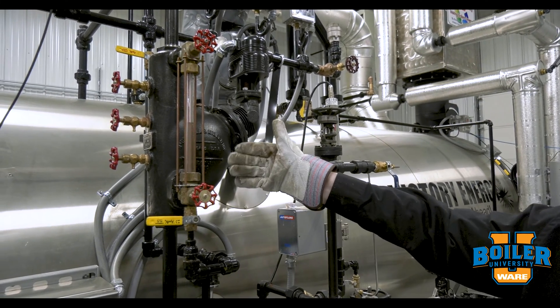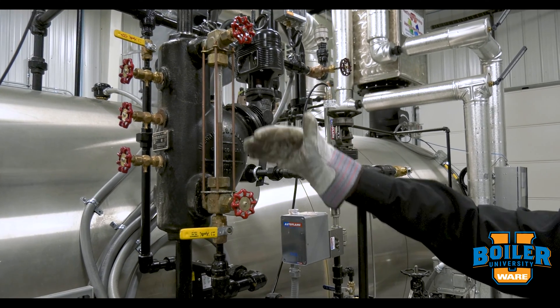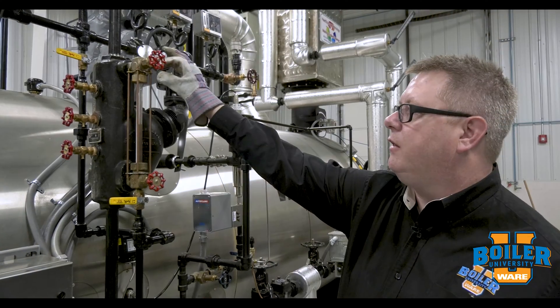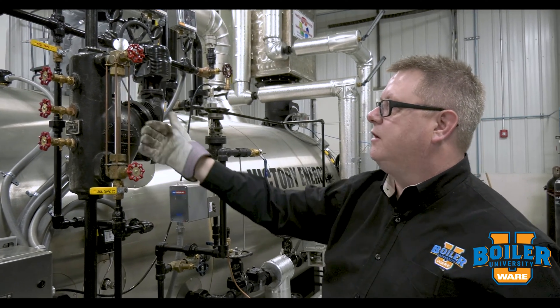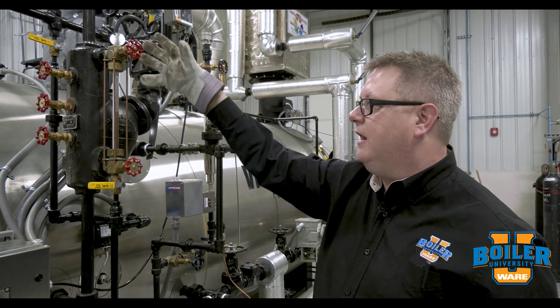Now occasionally when I blow down the sight glass, the level will remain full or it will flood all the way. That may be the result of our safety ball check. These stop valves have a ball in there so that if the sight glass is shattered or cracked, the velocity of liquid or steam leaving will pull that ball into the socket and isolate it.